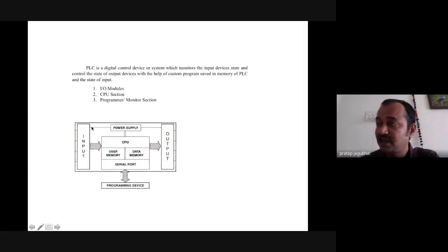Now, I would like to give a little more glimpse from the PLC point of view. This is one of the very widely used digital control systems, and it was invented to overcome the erstwhile relay logic. With relay logic, we used to prepare a relay wiring diagram in the panel, with a fixed set of strategy for that kind of structure. To overcome that, the programmable logic controller was defined, where you can have similar functionality in a user-configurable and more flexible manner, where your fixed IO can be set for any kind of application and changed later on also.